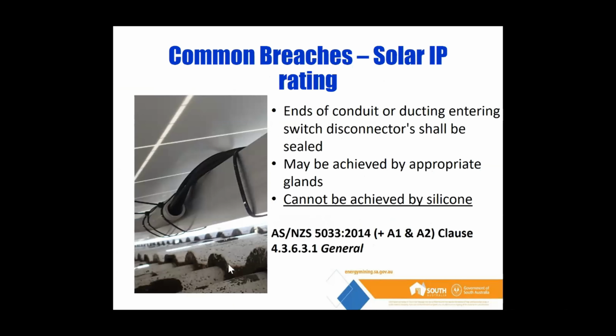This here is purely for the solar guys, and it's unfortunately a pretty common breach that we find, and it's guys not sealing the entry of a switch disconnector. Now that switch disconnector could be on the rooftop, or it could even be down on the ground. Or it could be 300 meters away. It doesn't matter. At the end of the day, the opening of that conduit hasn't been sealed correctly, and it's under the panels. So yep, rain's not going to get to it, but we still possibly have the opportunity for condensation to enter into that enclosure. And for those of you that work with solar would know that water is our enemy in a switch disconnector. Therefore, that's why we need to seal the entry points of our DC enclosures and switch disconnectors.